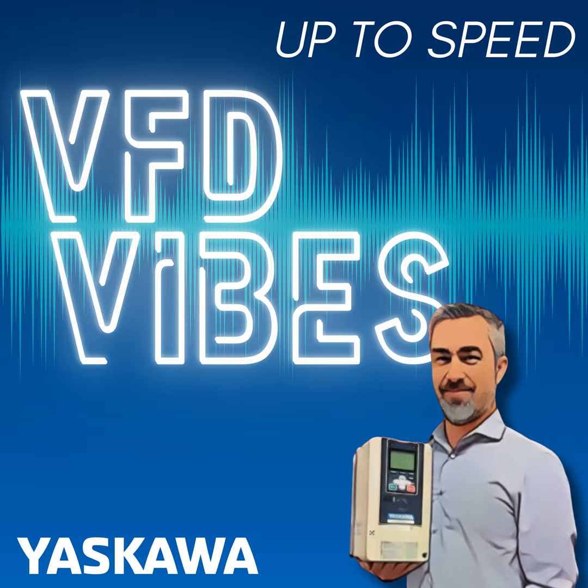on a single-phase source. Now, Yaskawa does have a product which is called the single-phase boost converter, which is designed to actually convert that single-phase AC into a regulated DC bus that can now power the drive through its DC terminals. We sell that product, and that product is used primarily in remote irrigation systems. And that's a solid-state product, too. Yes, correct, that's a solid-state product. It's not a rotary converter, so it's truly solid-state.